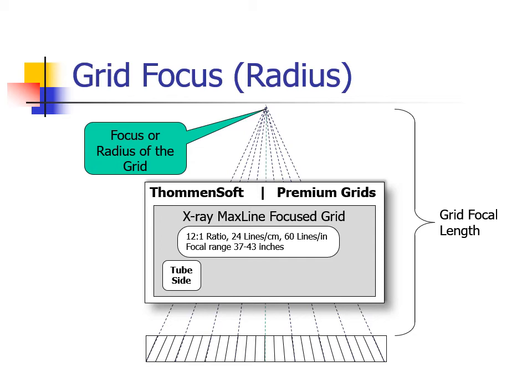Note that this grid has a tube side, and if the grid is incorrectly positioned with this side away from the tube, an extreme amount of grid cutoff will occur.